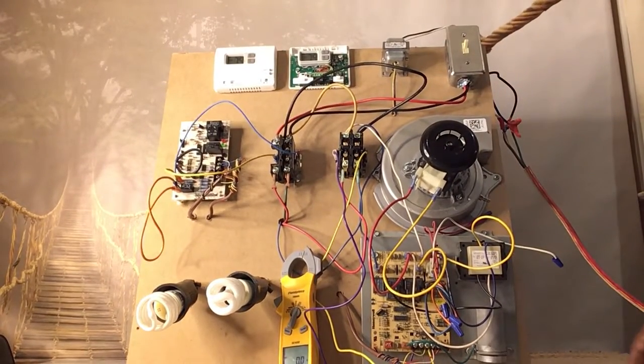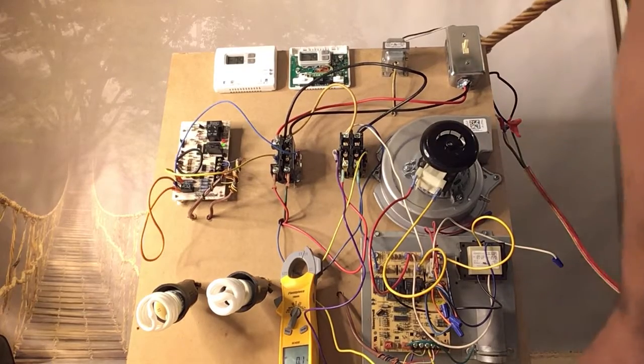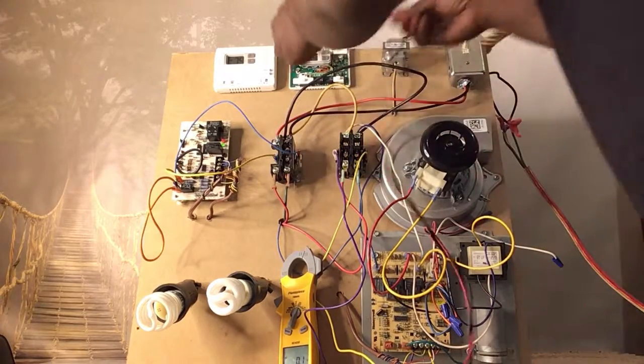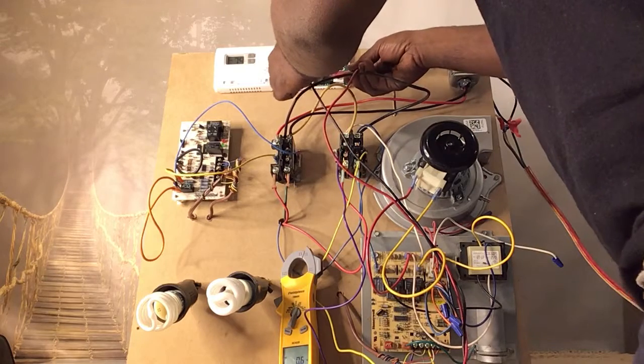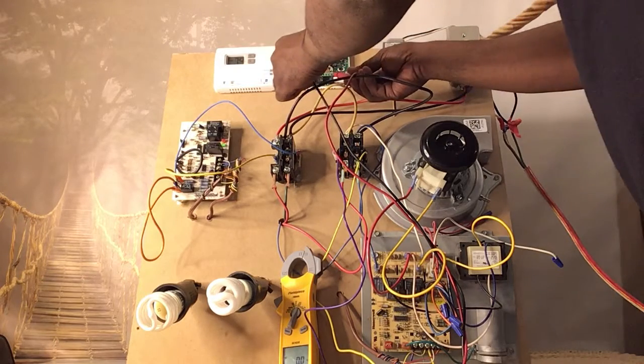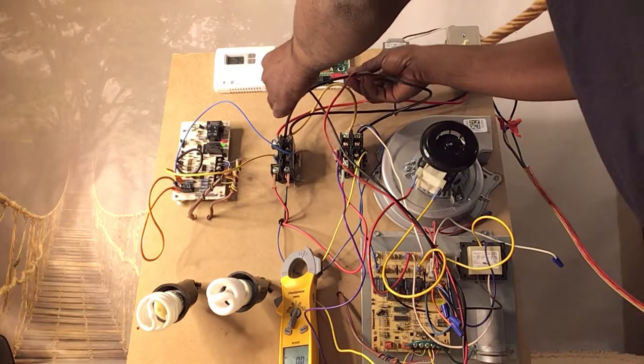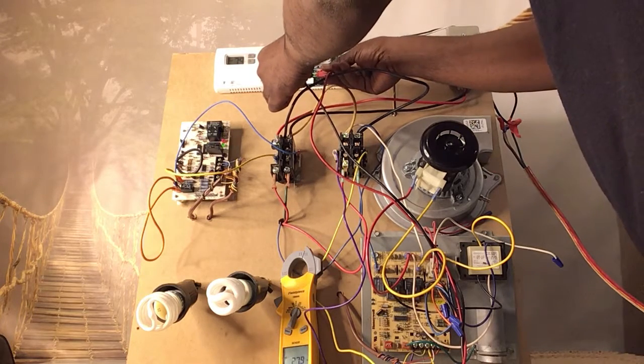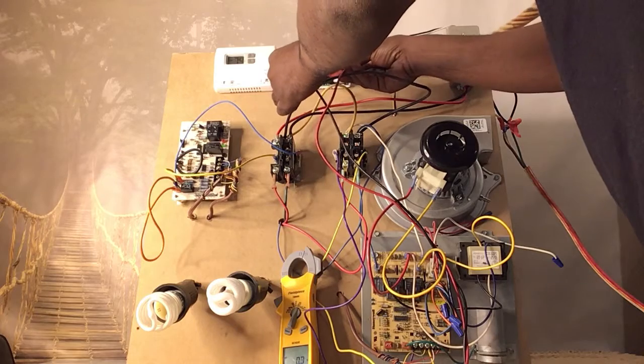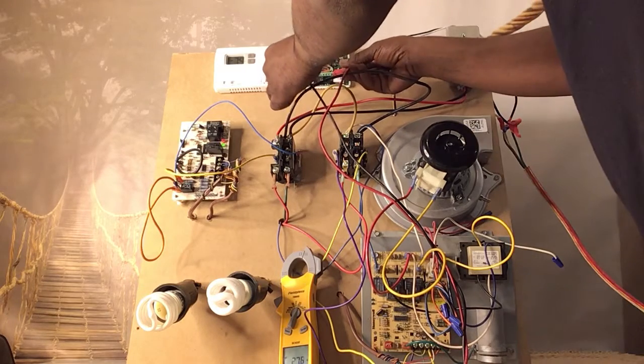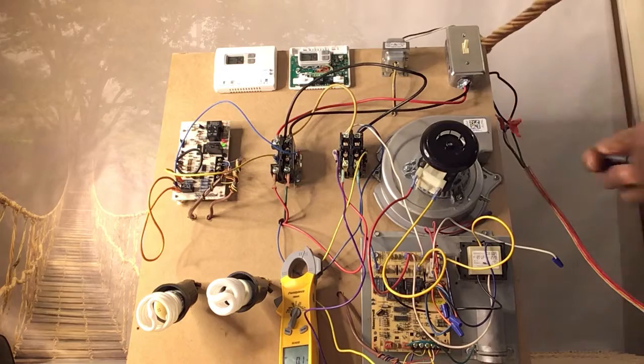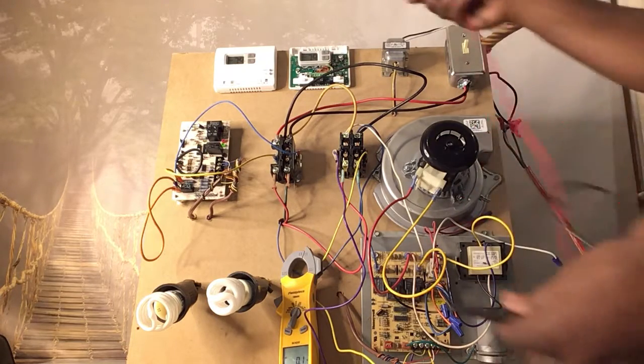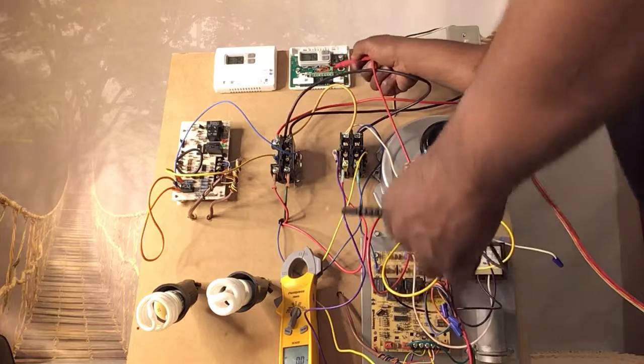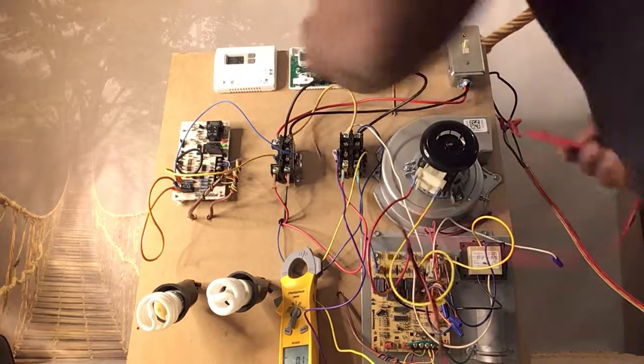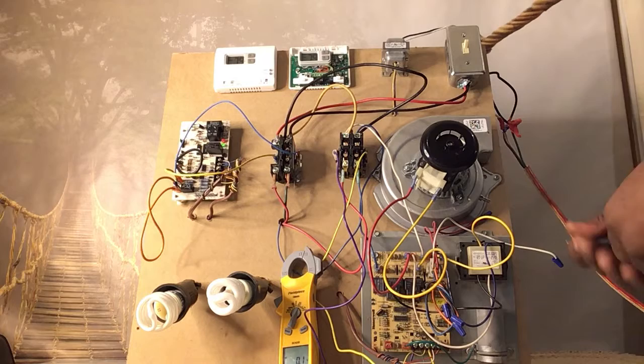So one more time, we're going to turn all this on. What I want you to focus on more than anything else is this. Right now, from common to yellow, we have 0 volts. No voltage here. From common to red, we have 24 volts. From red to yellow, we have 24 volts. Your thermostat, once it gets a call, is going to take power from the red and shift it over to the yellow. The common wire remains. It's just a ground wire. So we're going to turn this back on again.